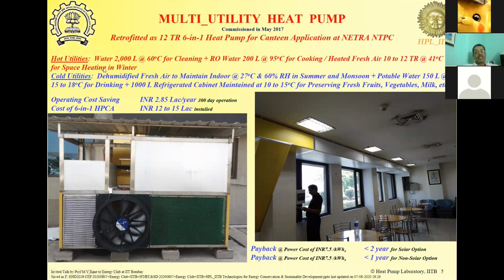Okay, similarly, we can deliver 2000 liters of hot water using this heat pump at 60 degrees for cleaning utensils, cleaning floor and other sanitary needs for the canteen. RO water is also heated in a once-through mode right up to 95 degrees centigrade. So you take this 95-degree water, you put some rice in it, and it can cook itself without you having to heat it up again. You can use this for cooking various other vegetables and various other items. So hot water for cooking, 200 liters per day.